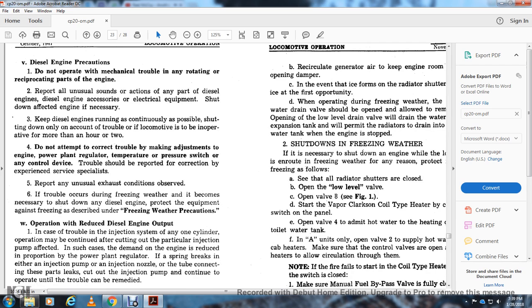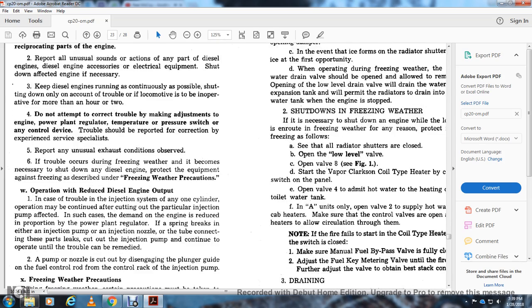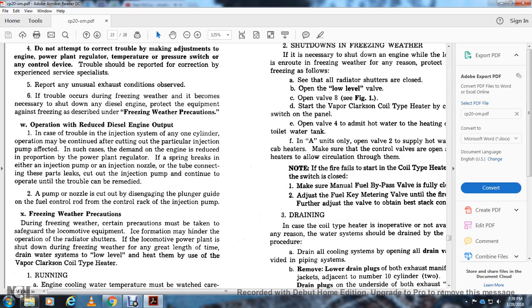When operating with reduced diesel engine output in case of trouble in the injection system with one cylinder, operation may continue with the particular injection pump cut out. The effect in such case is that the demand for the engine is reduced in proportion to the power plant regulator. If a spring breaks, or either the injection pump or the injection nozzle, or the tube connections or part leaks, cut out the injection pump and continue to operate until the trouble can be remedied. 2. To cut out the pump nozzle, disengage the plunger guide with the fuel control rod from the control rack for the fuel and for the injection pump.